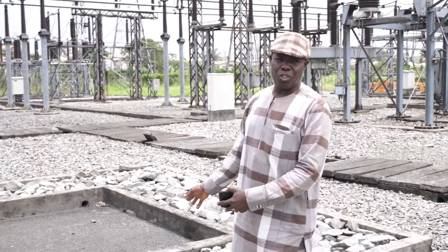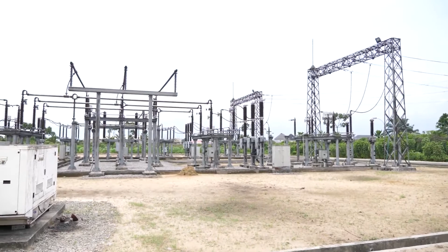So this is the plant already, it's already there. All we are after now is the arrival of the transformer, and then the other accessories - circuit breaker, CTs, isolators. Once those materials are available, we'll commence the job to install the 100 MVA here, so that we have 2 by 60, then 1 by 100 in Port Harcourt main.